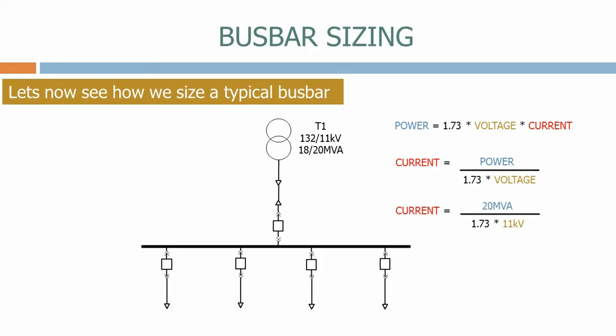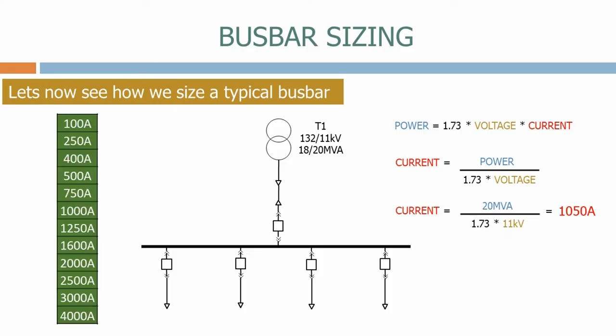For transformer T1, the current equals the maximum rating of 20 MVA, divided by root 3 times its maximum voltage, which is 11 kV. The maximum current is 1050 amps, which is the peak current that will flow through the busbar. The busbar manufacturers make them in standard ratings. Looking down the table, the busbar we should choose for this application is 1250 amps.